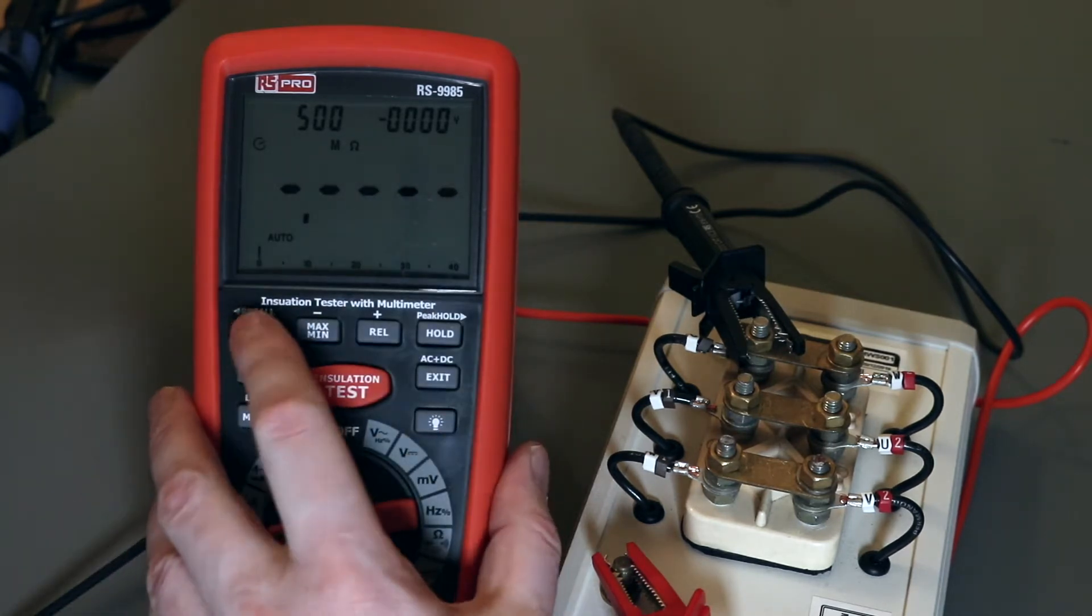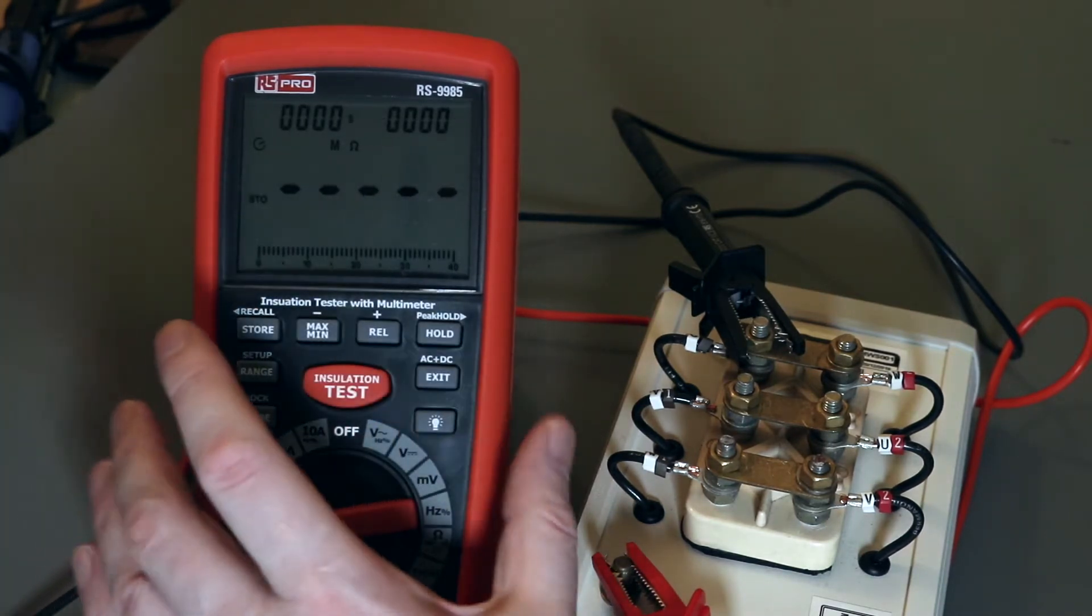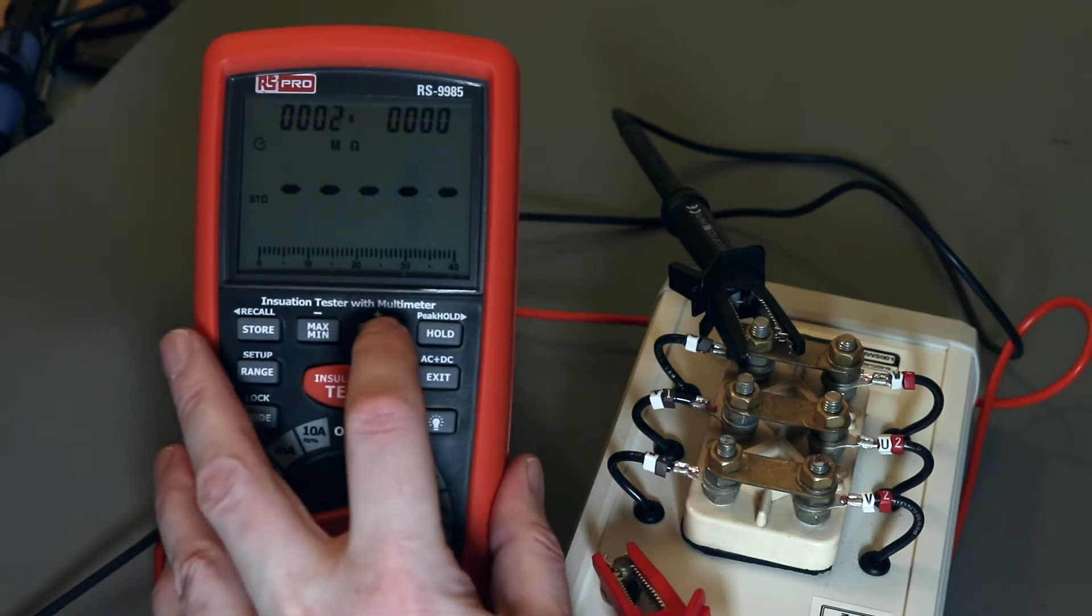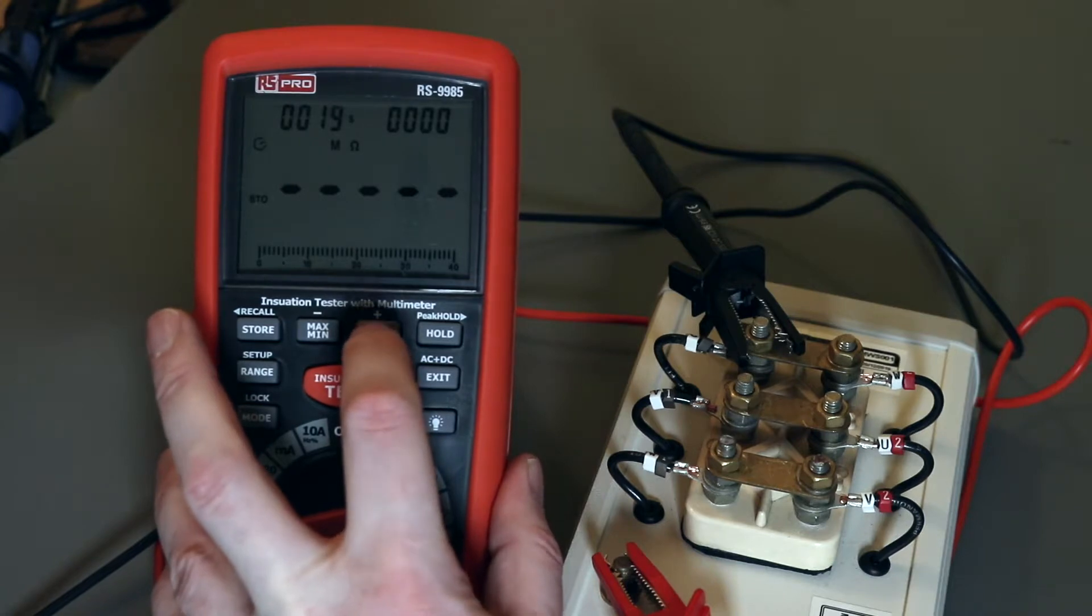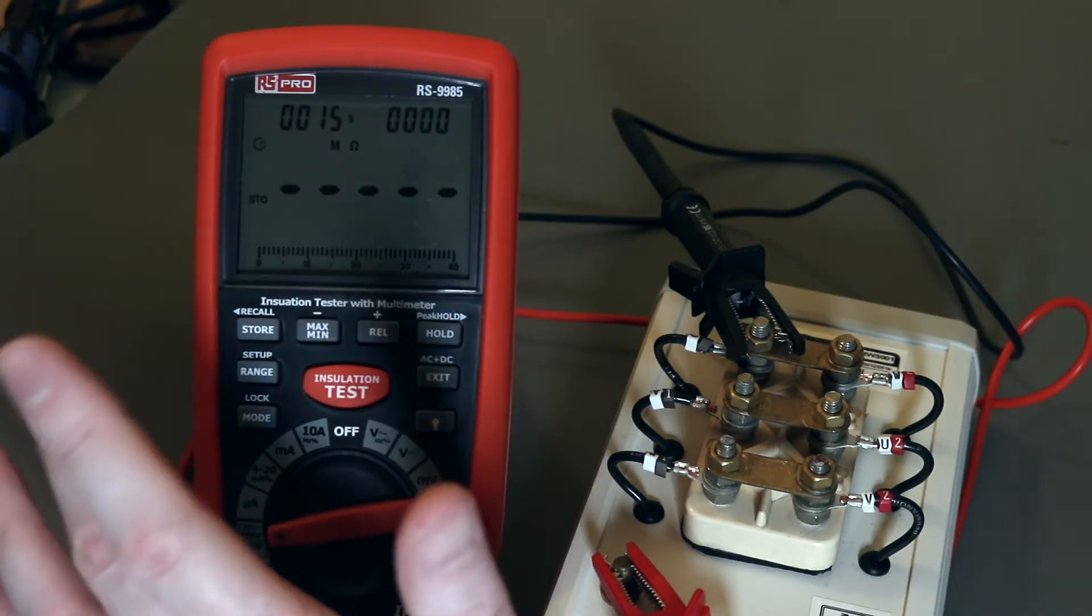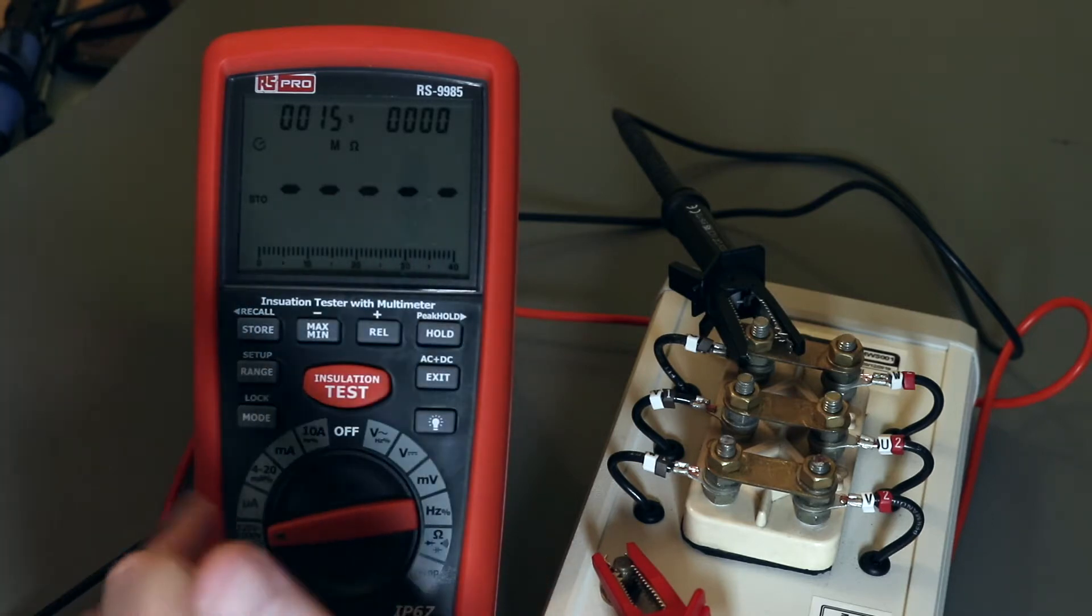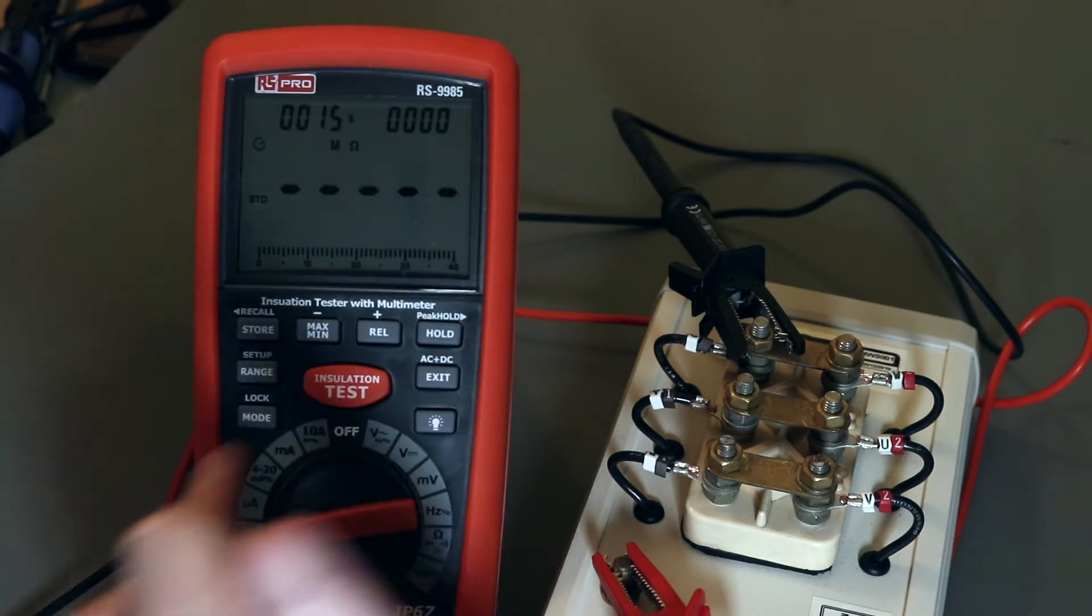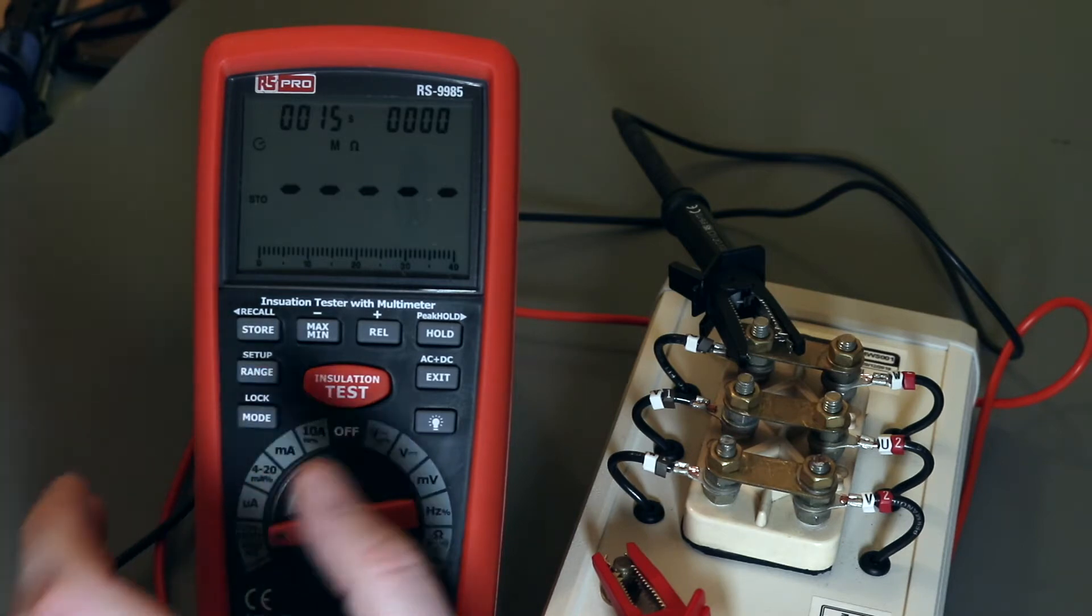So to do that, I'm already in insulation test mode. Go to store. And this time I'm going to set it up to read every 15 seconds. And that's that one there. So the moment I hit the store button again, it's going to start that 15 second count. So I have to hit the store and start the insulation test almost immediately.